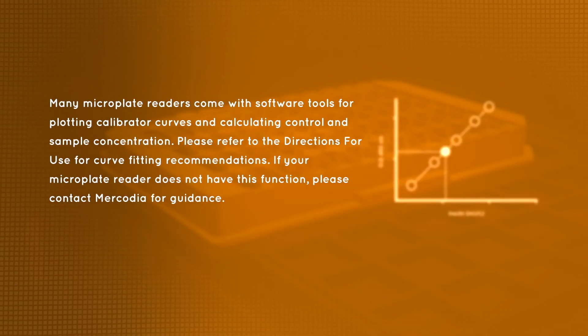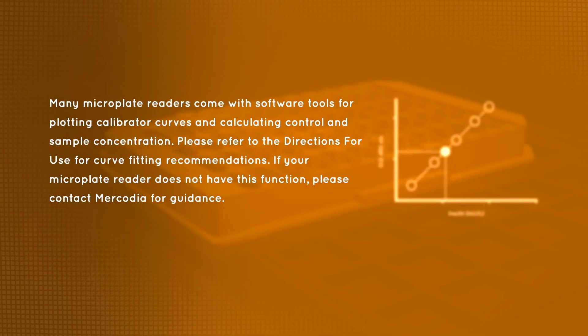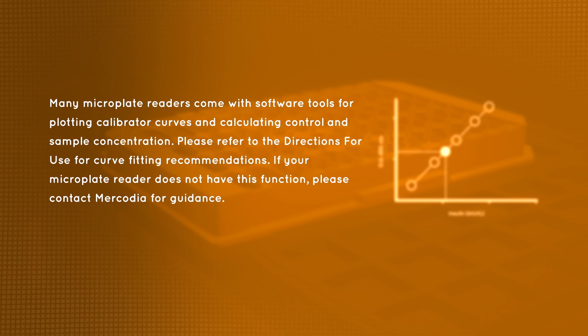The calibrator curve is plotted using values for all calibrators except calibrator zero. The curve is necessary for determining control and sample concentrations, and thus calibrators must be included in every run.